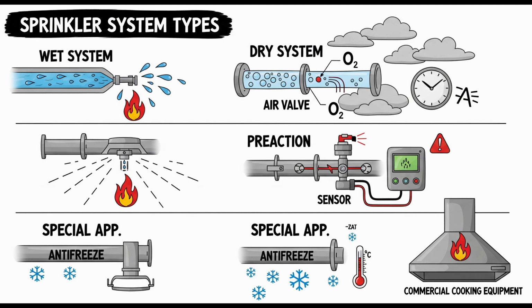What about temperature ratings and K factors for these kitchen protection sprinklers or nozzles? It must get incredibly hot in those hoods and ducts. It certainly does. The standard requires that where the normally anticipated temperature exposure during cooking operations is 300 degrees F, about 150 degrees C or less, the sprinklers or nozzles used in the duct, collar, and plenum areas must have an extra high temperature classification. These are typically rated to activate somewhere between 325 degrees F and 375 degrees F, which is 163 degrees C to 191 degrees C. Extra high temp is the minimum starting point.